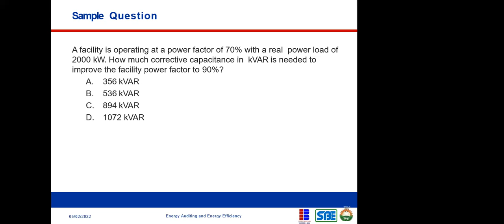A facility is operating at a power factor of 70% with a real power load of 2,000 kilowatts. How much corrective capacitance in kVAR is needed to improve the facility power factor to 90%?